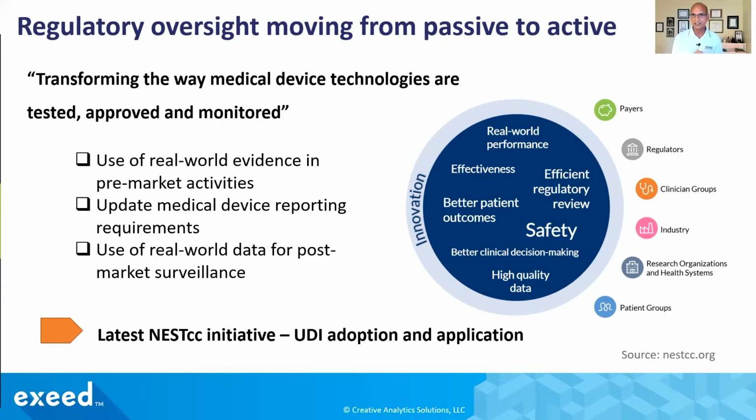Please share your thoughts. Well, Naveen, I can say that when we developed Clause 10 of 14971, we had this in mind, that it would be active, that you could not wait for complaints to come in, but you had to go out and seek information on your device.